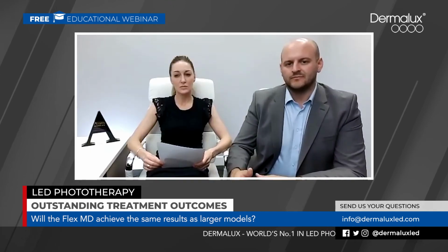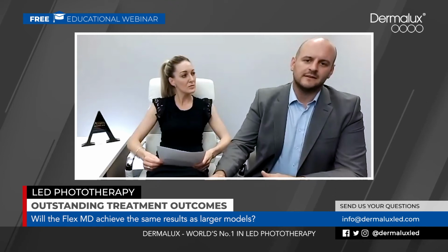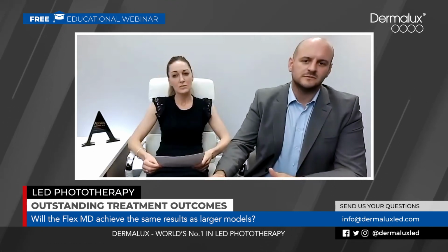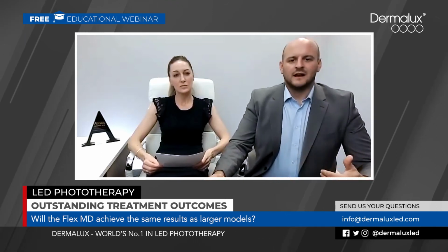To give you that as a comparison, your next stage up is either the Compact or the Triwave. That's a halfway power point to the Triwave MD, the largest device we sell, and that's only a 20-minute cycle. And then as you move up to the MD, the maximum amount of power: if you turn all three LEDs on for a 20-minute cycle, it's 240 joules per centimetre square collectively over a 20-minute period. Whereas if you had all 3 colours on the Flex, you're only at 40 joules per centimetre square collectively over a 30-minute period. So you can see the big difference in the overall power being emitted on the device.